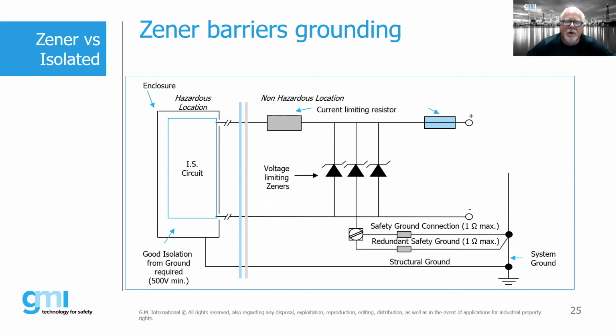No. The IEC standards for IS are 60079-14 and 60079-25. Basically what the -14 standard says, and I believe -25 says the same thing, is that it should be tested periodically. If somebody says their practice is to do it every 6 months, that very well could be a situation where a client, a country-specific standard, or some regulation in that particular country says you must test it every 6 months. Quite honestly, I have not seen that, and it's very unlikely that people are going to be testing the quality of the ground every 6 months. But if that's a requirement, it's an expensive exercise, and it would be pretty onerous to have to do.